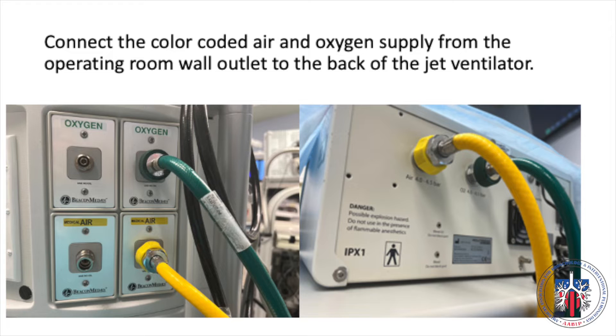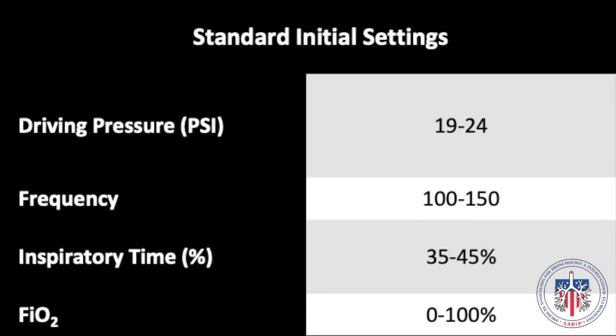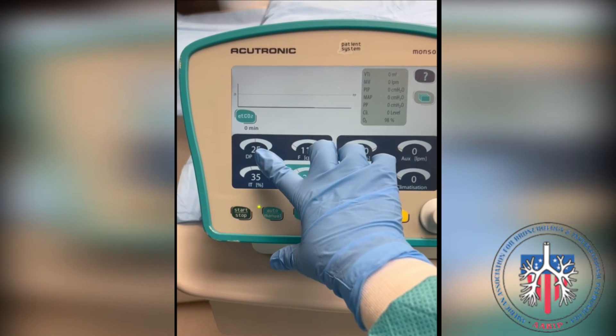Connect the color-coded air and oxygen supply from the operating room wall outlet to the back of the jet ventilator. Standard initial settings are a driving pressure of 19 to 24 psi, a frequency of 100 to 150, an inspiratory time of 35 to 45 percent, and an FiO2 of 100 percent.